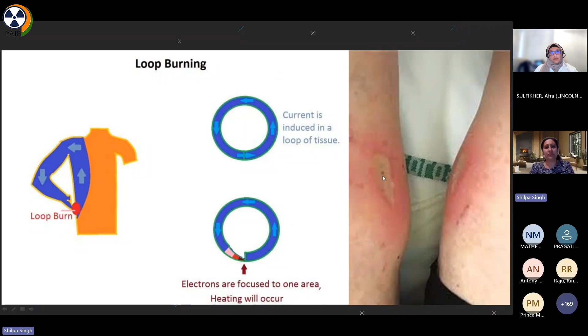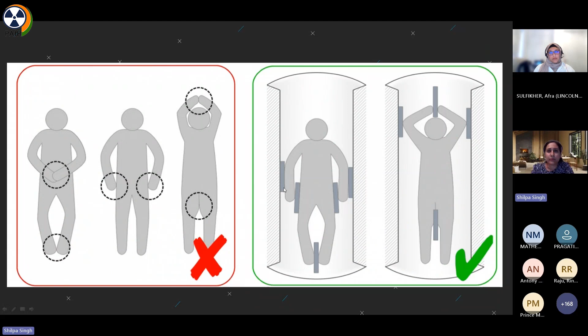Whichever body part is touched and converted into a loop can heat up to the extent of a burn. So you can see both the legs seem to be burned. That is why we have the non-conductive foam pads available in MRI, which are to be placed between the arms and between the legs. And there should be no loop formation which would allow the current to flow. No legs crossing, no holding hands, no hand touching the waist or any other part of the body. Also, if you look carefully, the patient has also been given non-conductive pads next to the MRI bore. Why? We will see that later.